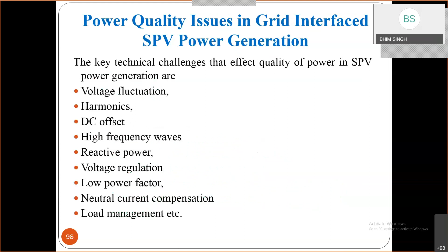And of course, you have other power quality problems you can think about. This is the first system we looked into, a single stage. You have a solar panel and a converter. We were working on power quality for more than a couple of decades, so we thought, why not use this inverter for 24 hours? Not only for solar generation, but also for taking care of power quality issues, compensating the local load, and feeding power to this local load. It means the power taken from the grid will reduce, and it takes care of harmonics and reactive power of this load so the grid current is at unity power factor.